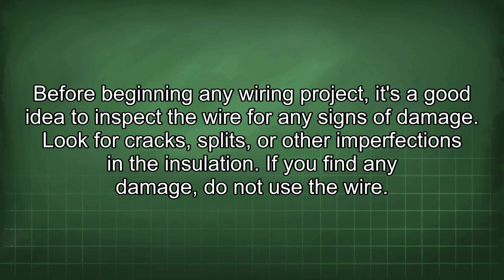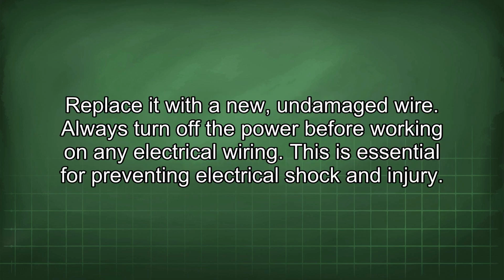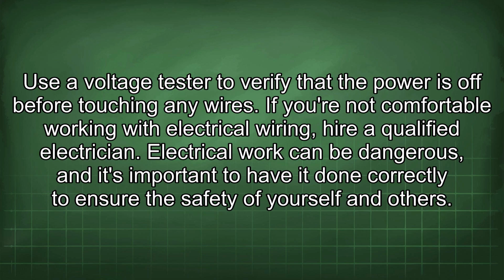Before beginning any wiring project, it's a good idea to inspect the wire for any signs of damage. Look for cracks, splits, or other imperfections in the insulation. If you find any damage, do not use the wire. Replace it with a new, undamaged wire. Always turn off the power before working on any electrical wiring. This is essential for preventing electrical shock and injury. Use a voltage tester to verify that the power is off before touching any wires.